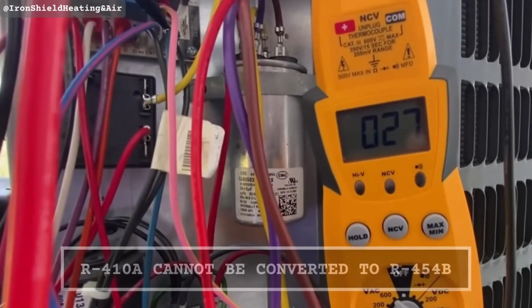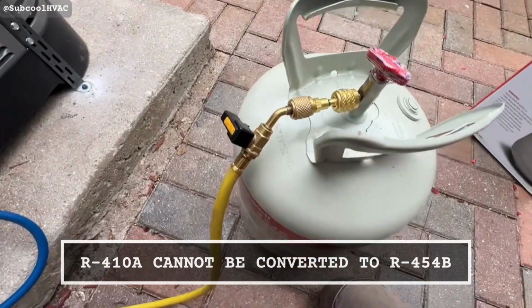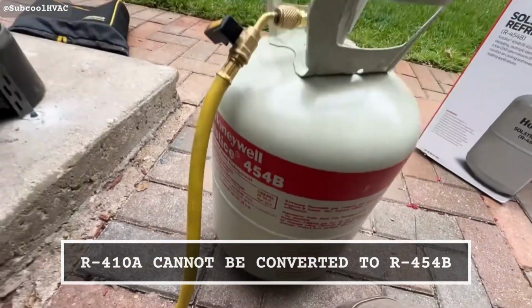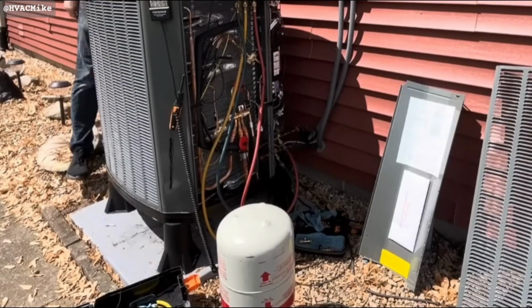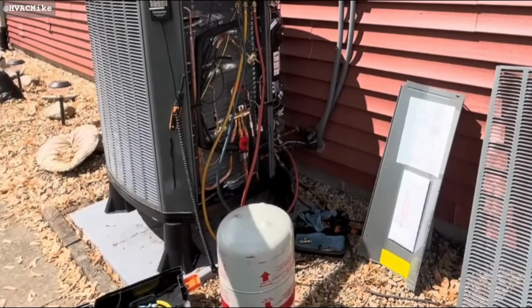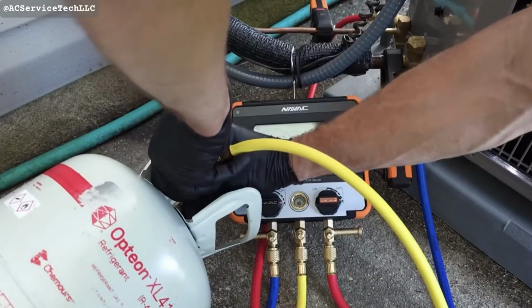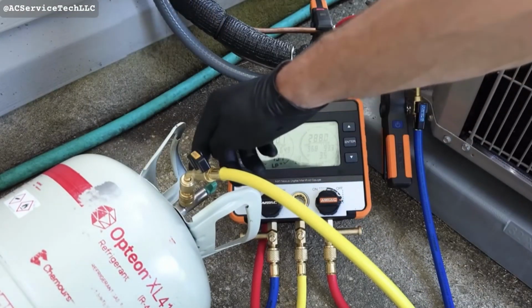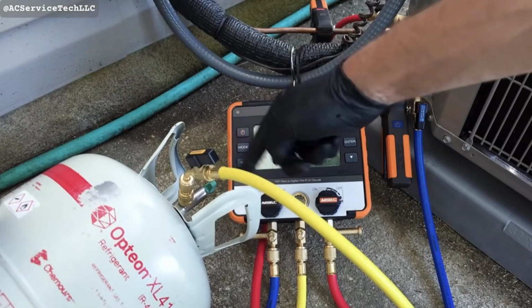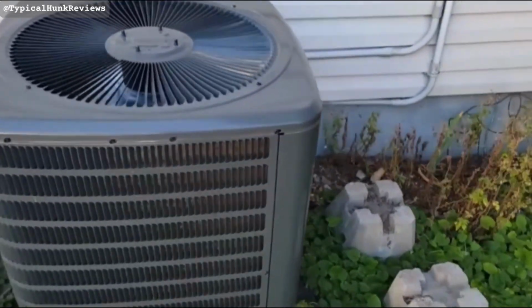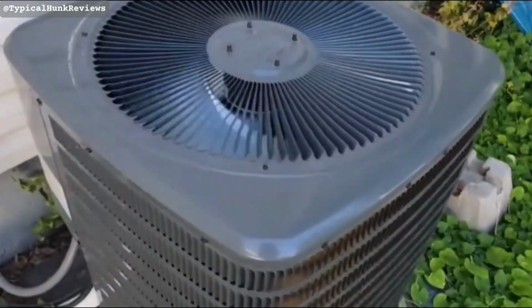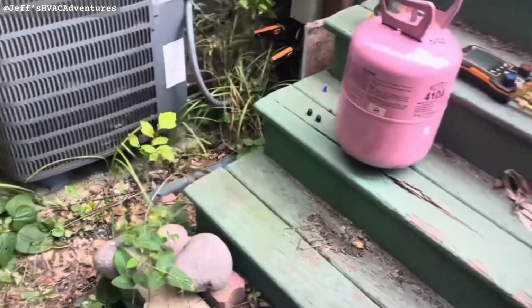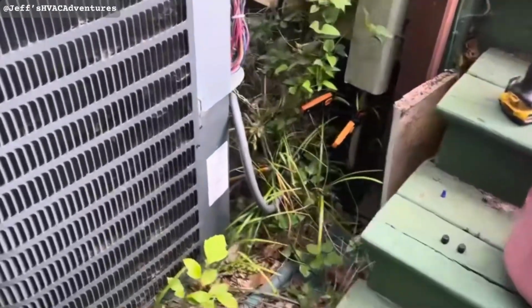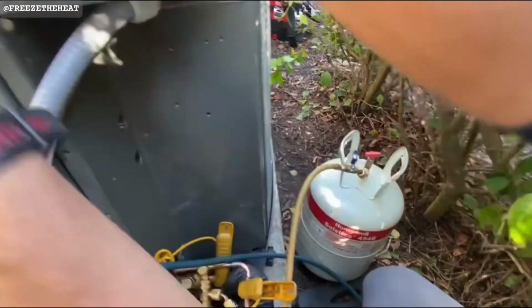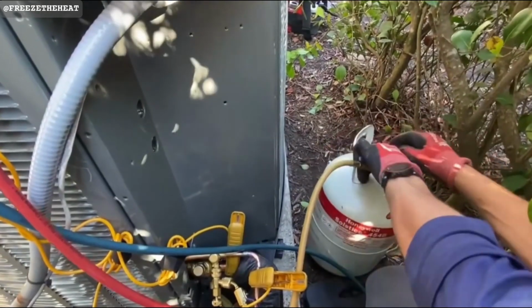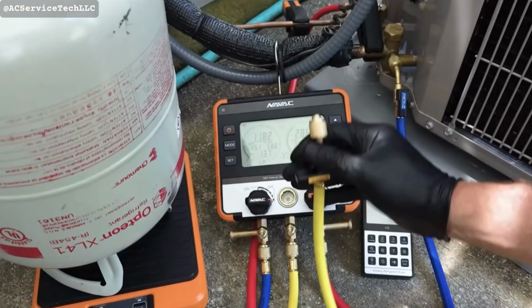Number 20. As of 2025, new HVAC equipment ships with R454B refrigerant, mildly flammable and classified A2L. R410A systems cannot be retrofitted to R454B. The refrigerants are incompatible at the equipment level. Contractors quoting you a retrofit on an R410A system are either misinformed or running a scam. A switch from R410A to R454B requires a complete equipment replacement, indoor coil, outdoor unit, and line set service.